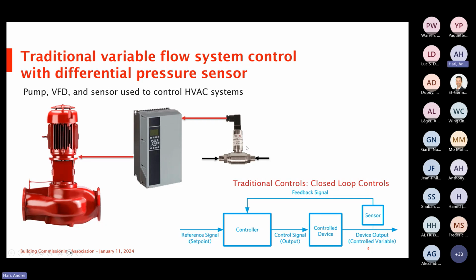As a valve opens or closes in the system, that pressure changes from one side to the other, and there's a set point deviation, either positive or negative. So that sensor picks up that deviation, sends a signal to the controller, which is the drive, and the drive then either speeds up or slows down the pump to get back to that zero set point. The key in all of this system, or in this traditional configuration, is that we don't know what the flow is unless we have a flow meter. The drive does not know what the flow is.